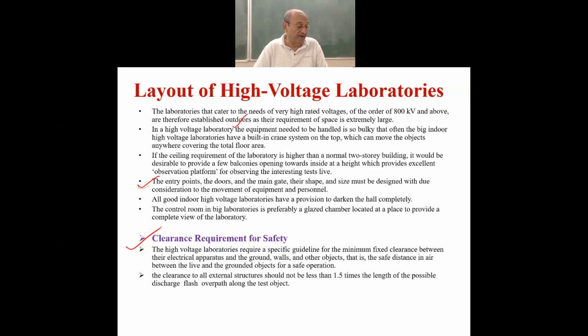So the total floor area requirement will be determined by the clearance. Once you set up the equipment and have taken care of the clearance, the equipment is not moved. All this equipment, for example the AC power frequency, DC and impulse voltage generators, is so big that once you place them, they are not movable. They are fixed at their places, and you must place them at the safe distance, that is, the clearance distance.